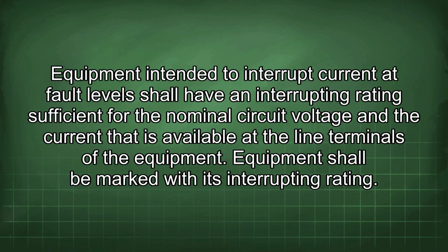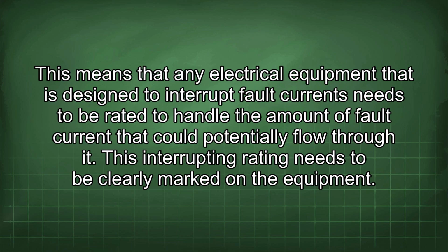Equipment intended to interrupt current at fault level shall have an interrupting rating sufficient for the nominal circuit voltage and the current that is available at the line terminals of the equipment. Equipment shall be marked with its interrupting rating. This means that any electrical equipment that is designed to interrupt fault currents needs to be rated to handle the amount of fault current that could potentially flow through it. This interrupting rating needs to be clearly marked on the equipment.